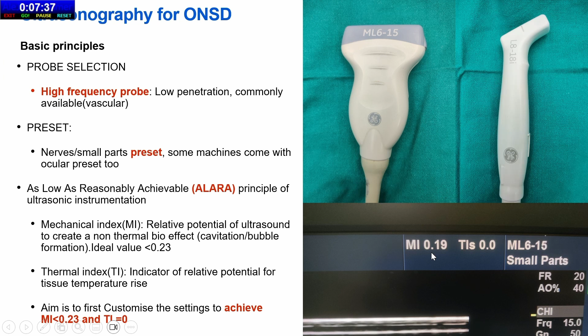Mechanical index, which is the relative potential of the ultrasound to create a non-thermal bioeffect, should be kept at less than 0.23. These are the figures seen on top of the machines at a corner. And thermal index, which is an indicator of a relative potential of tissue temperature rise, should be kept at 0.